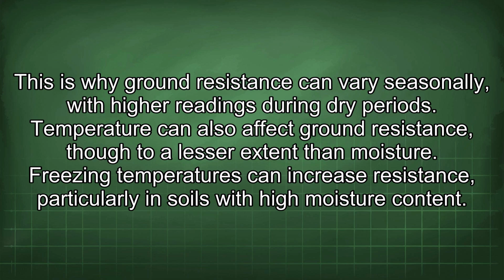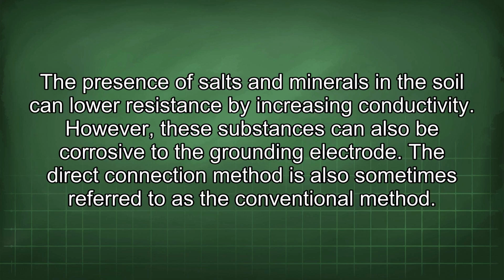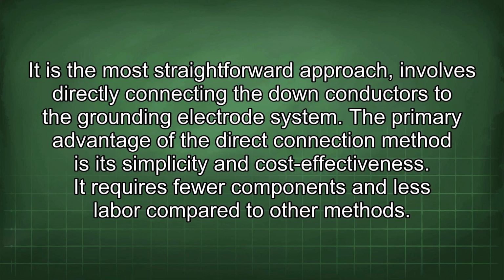Temperature can also affect ground resistance, though to a lesser extent than moisture. Freezing temperatures can increase resistance, particularly in soils with high moisture content. The presence of salts and minerals in the soil can lower resistance by increasing conductivity. However, these substances can also be corrosive to the grounding electrode. The direct connection method is also sometimes referred to as the conventional method. It is the most straightforward approach, involving directly connecting the down conductors to the grounding electrode system.